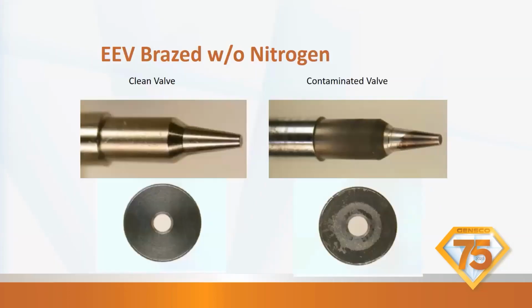This is an EEV brazed without nitrogen. You can see the contaminated valve, see all the black soot on there. You can see where on the seat, on the round part on the bottom, that's the seat, where that pin goes into the seat, you can see where there's black stuff around the opening. Well, there's going to be refrigerant going on the clean spots down in because it can't push through that soot. So it's going to actually cause it not to close all the way. This can actually get in there, and where the valve body is, this soot can actually build up there and then it'll stick part way. So it'll work sometimes and not work sometimes.